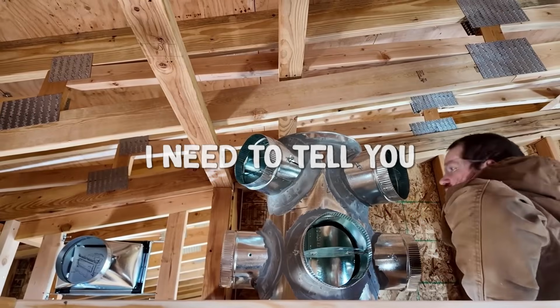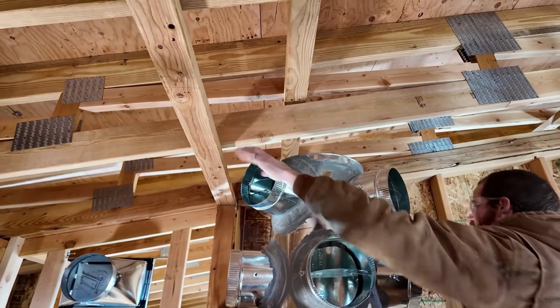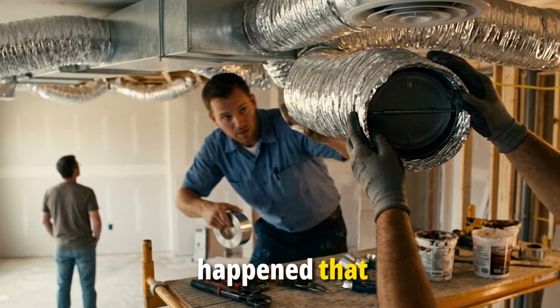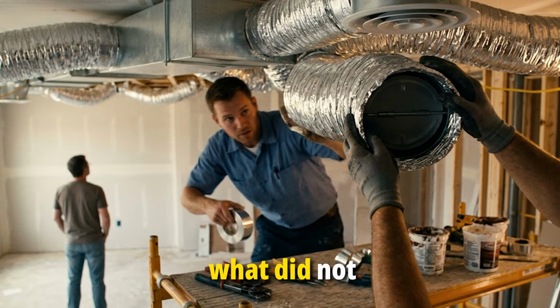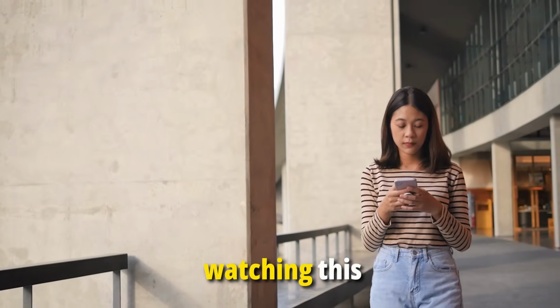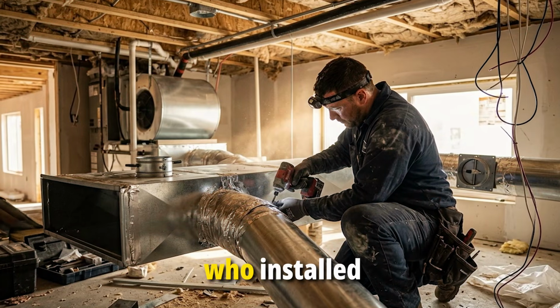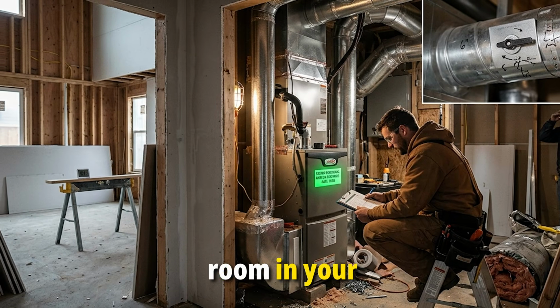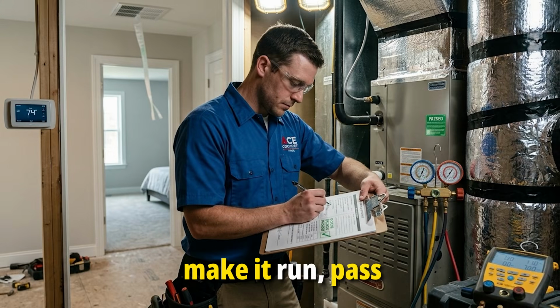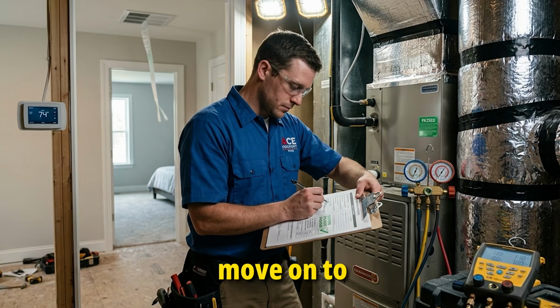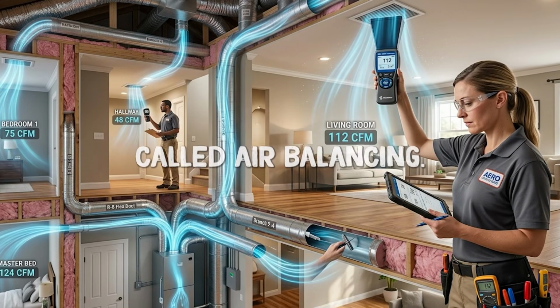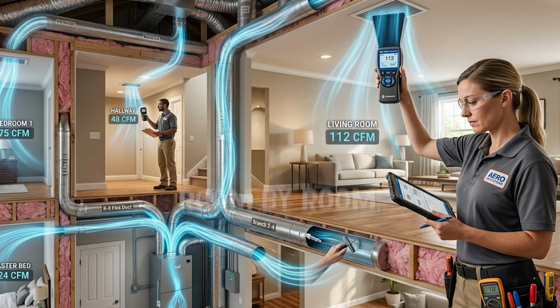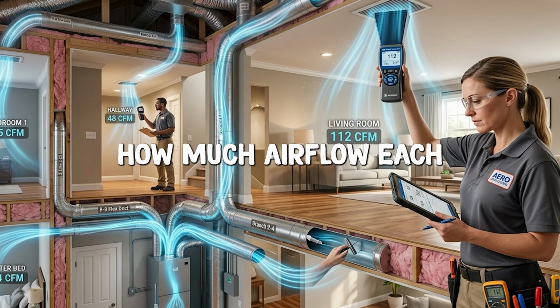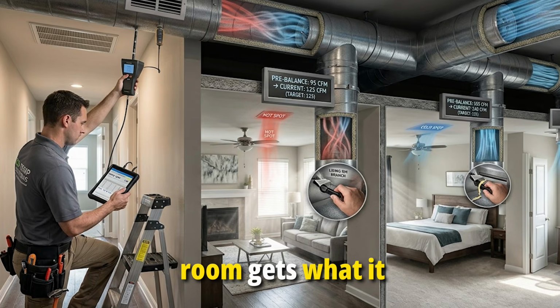But first, I need to tell you something about the day your HVAC system was installed. Because what happened that day, or more accurately, what did not happen, is the reason you are watching this video right now. The technician who installed your system was paid to make it run, not to make it work well, not to make every room in your house comfortable, to make it run, pass inspection, and move on to the next job. There is a process called air balancing. It is the work of going room by room, measuring how much airflow each space is actually receiving, and adjusting the system until every room gets what it needs.